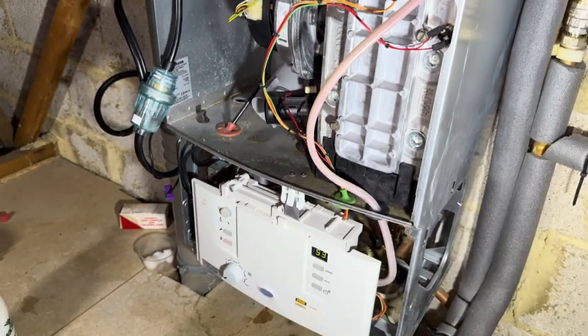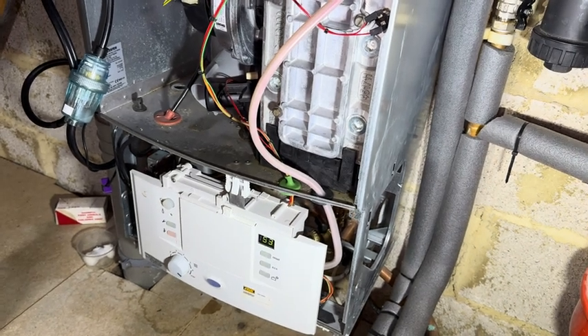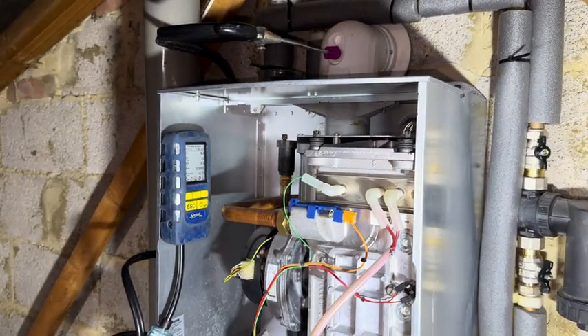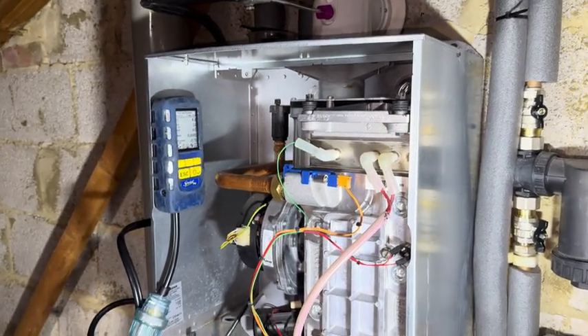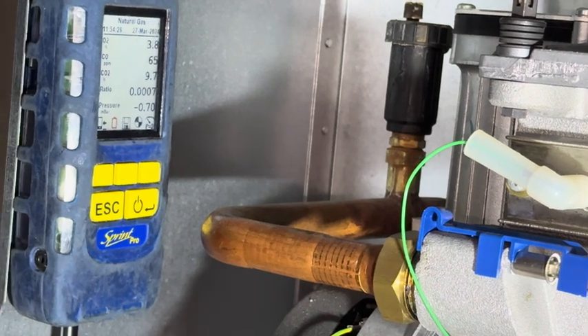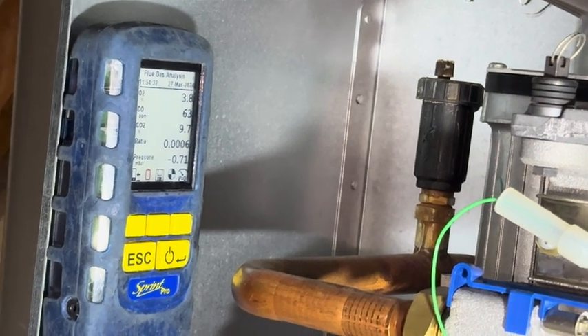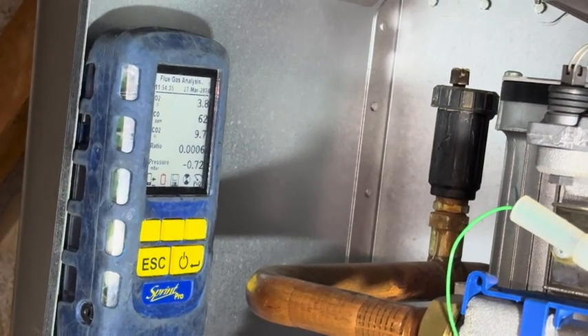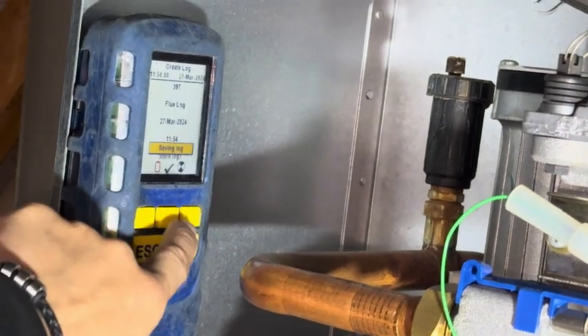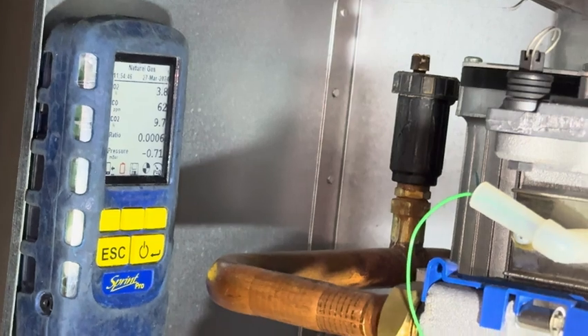We then turn it up to maximum — turning the dial to max, see the six lines or three lines come again. Now the CO has stabilized, we'll save that as well. We've got good analyzer readings all in line with the manufacturer's instructions.